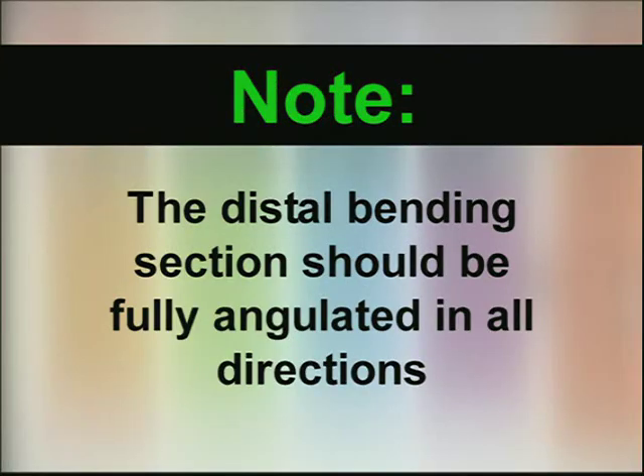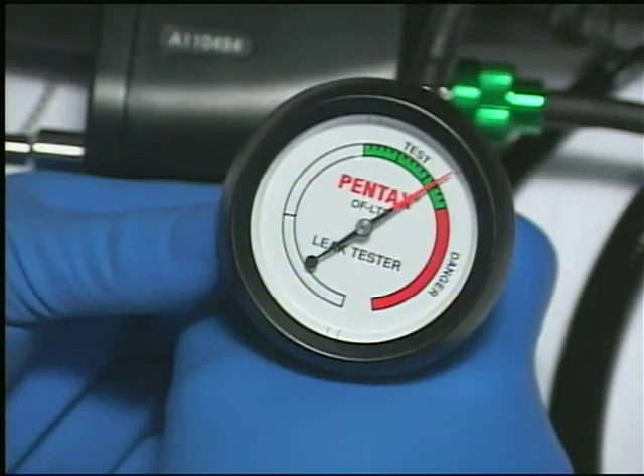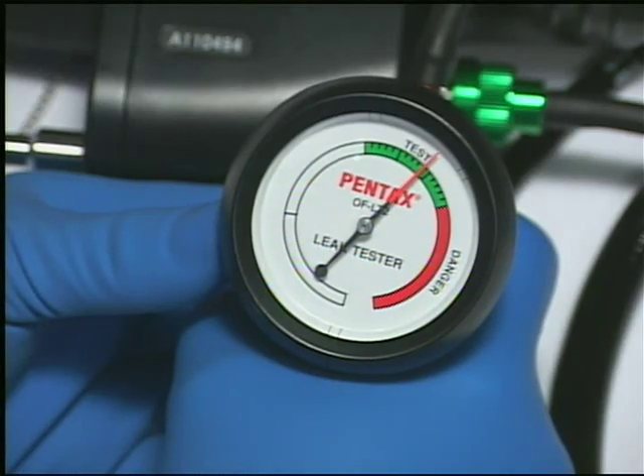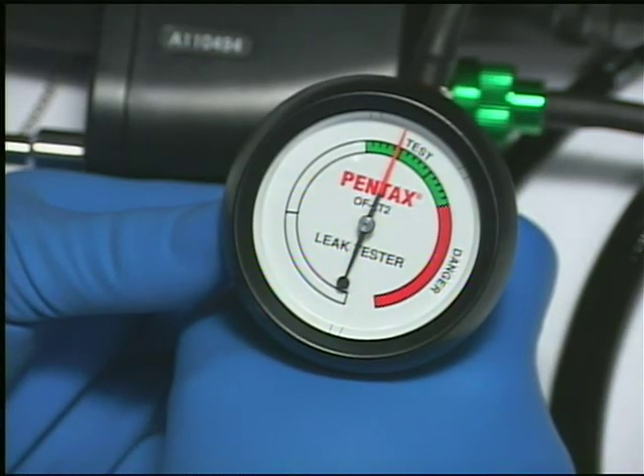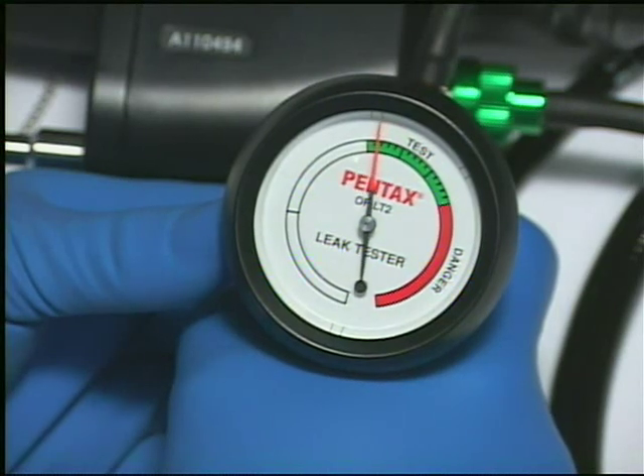Note: during the leak test procedure, the insertion tube of the scope should be flexed in various positions, and the distal bending section should be fully angulated in all directions to confirm the absence of a leak. Observe the gauge pressure to determine if the indicator remains in the green zone. If the indicator drops rapidly from the green zone, a major leak may be indicated.